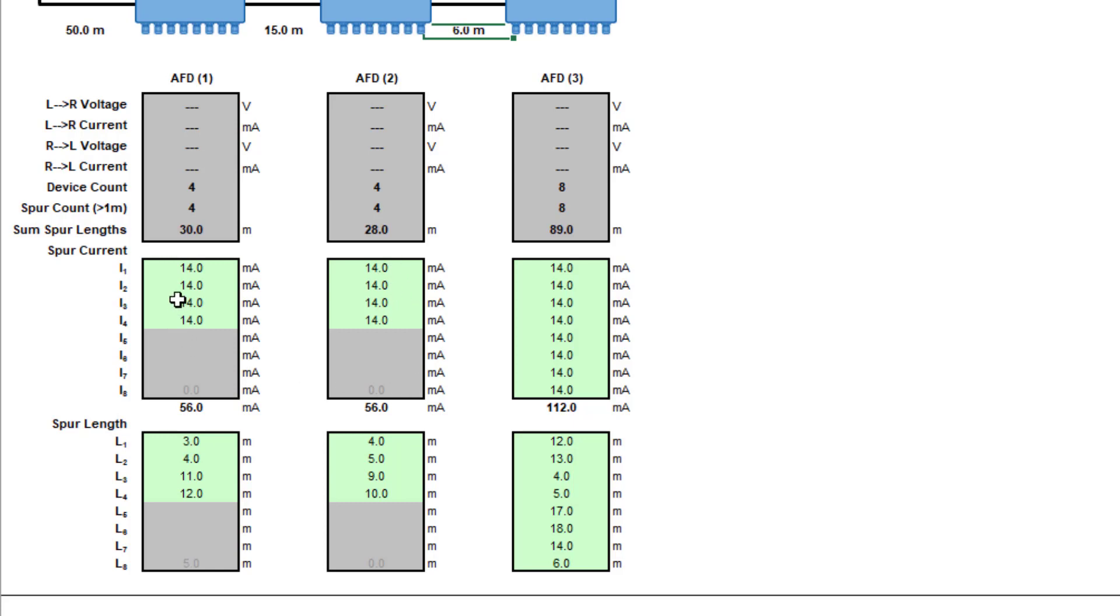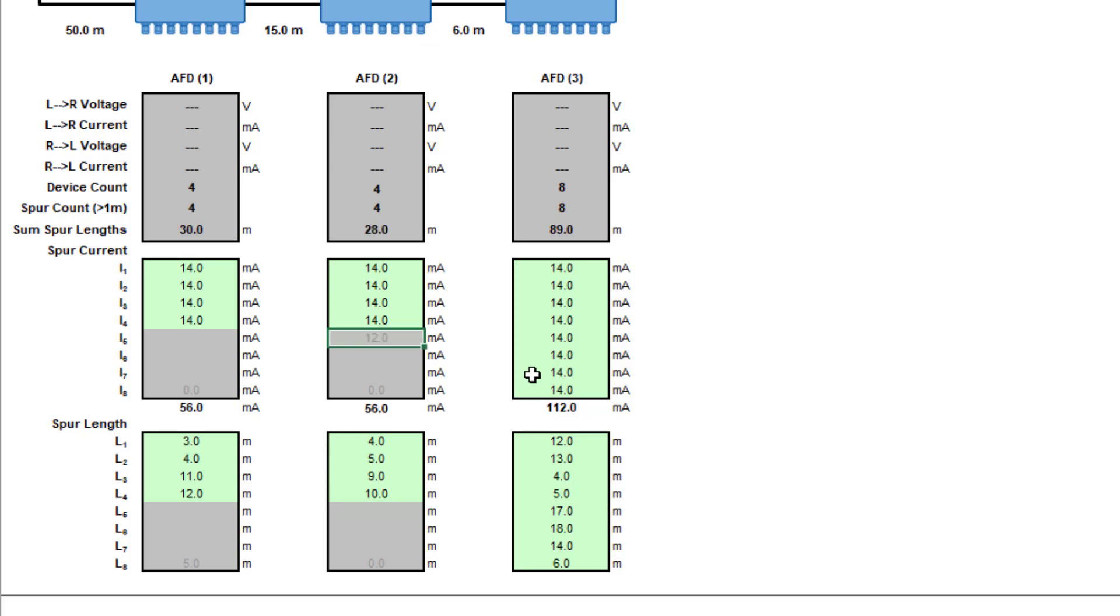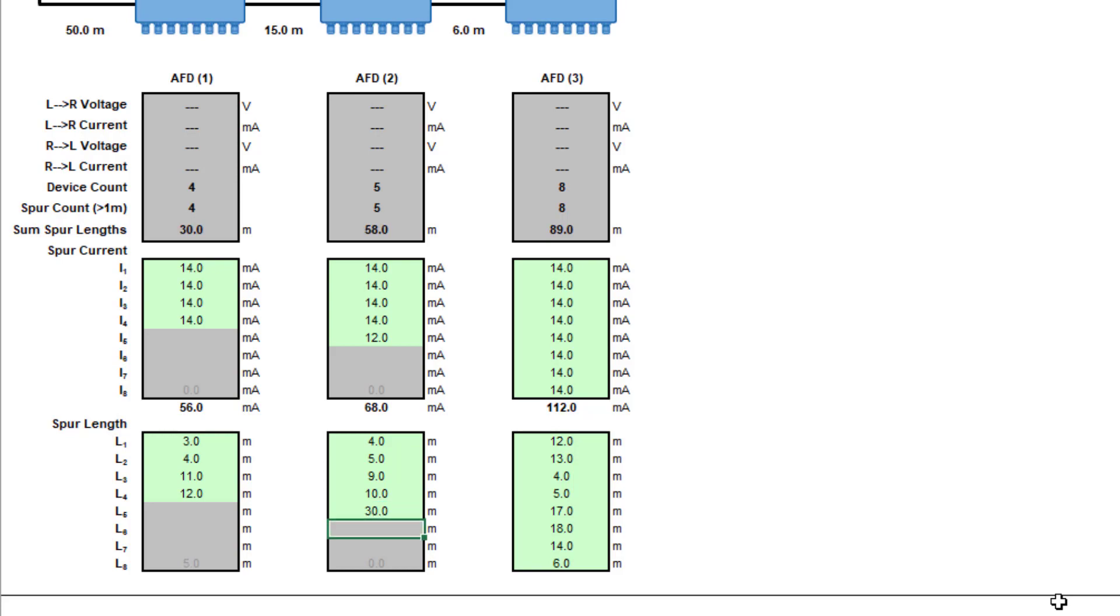For this example, I'm not using all of the connections on the eight channel. If I was going to use this, I could put in here 12 milliamps, and that now needs a spur length. For this example, I'm going to give that a bizarre spur length compared to the others of 30 meters.